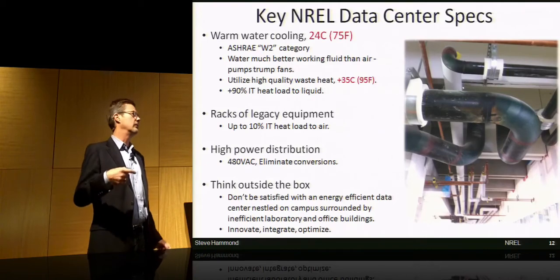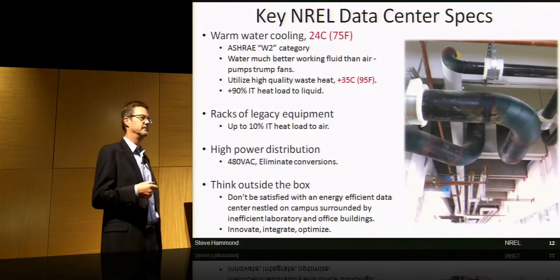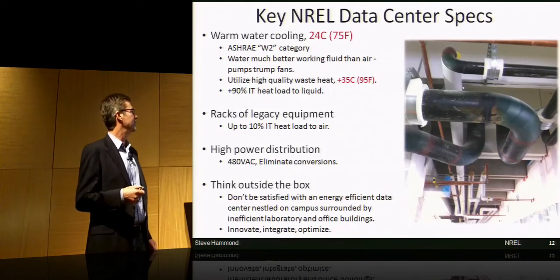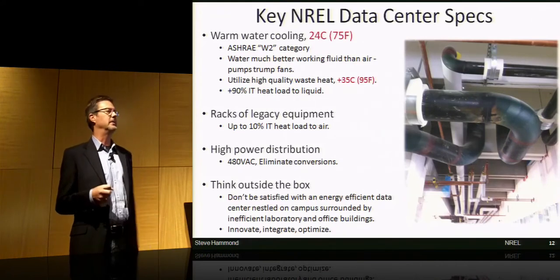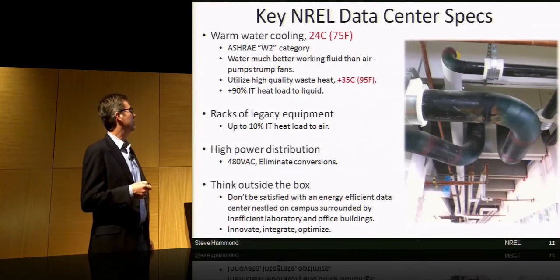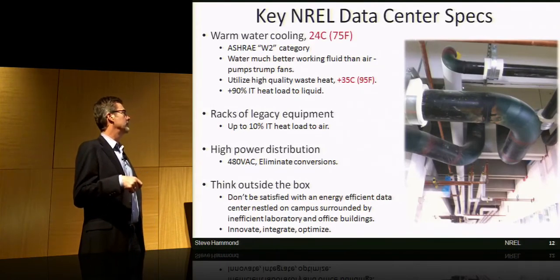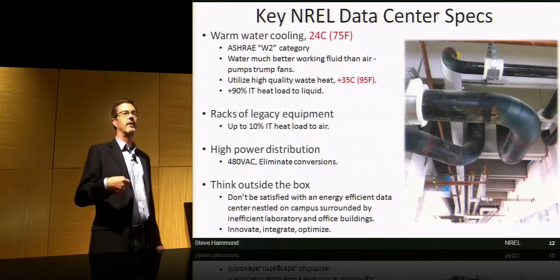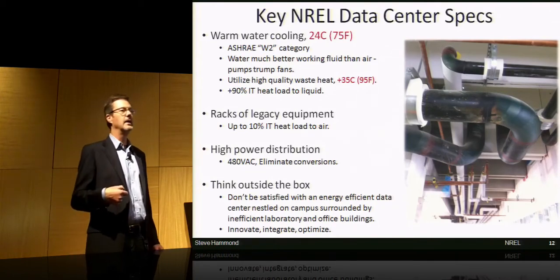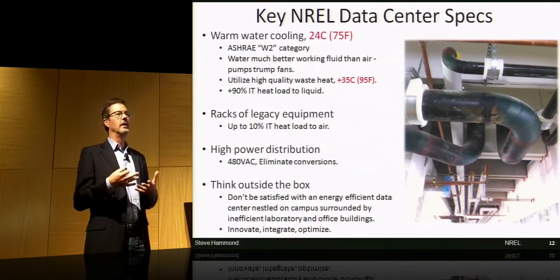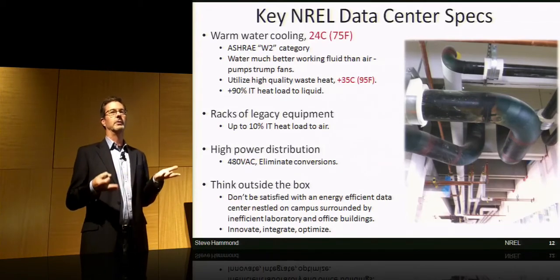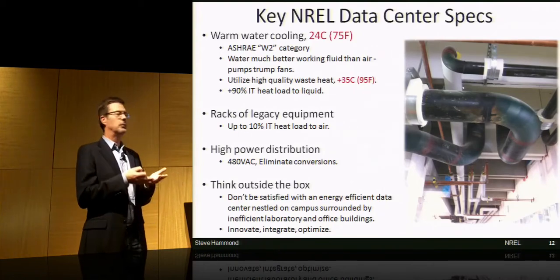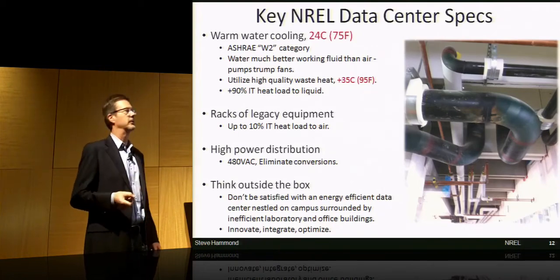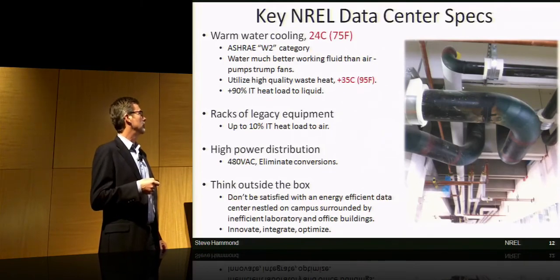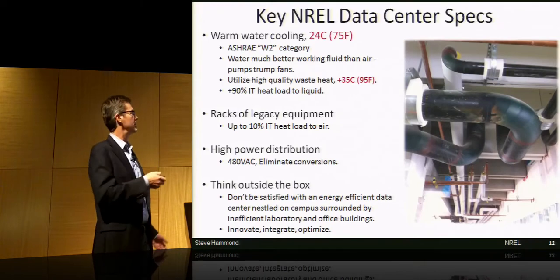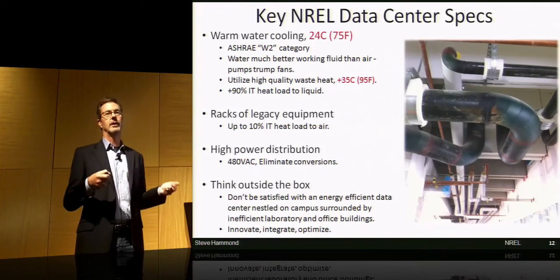Our primary water circulation is a 40 horsepower pump, so it's not a lot of complicated infrastructure. Maybe it's elegant in its simplicity. The other side is we're utilizing waste heat, so we want at least 95-degree water back off of the system. That was part of the interplay between what we could do using evaporative cooling only and what the building needed for heating. We need that minimum 20-degree difference from supply and return, so with the HP Apollo system we're capturing over 90% of the heat load directly to liquid.